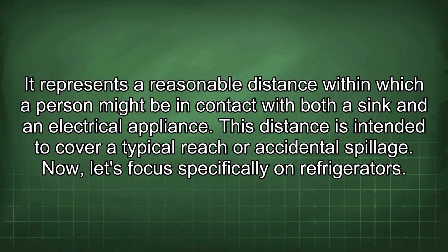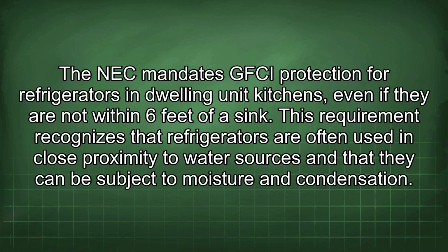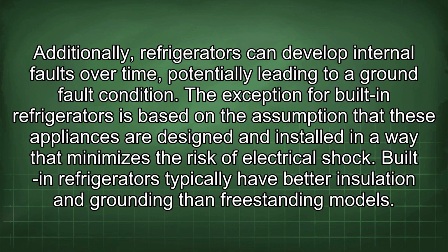Now, let's focus specifically on refrigerators. The NEC mandates GFCI protection for refrigerators in dwelling unit kitchens, even if they are not within 6 feet of a sink. This requirement recognizes that refrigerators are often used in close proximity to water sources and that they can be subject to moisture and condensation. Additionally, refrigerators can develop internal faults over time, potentially leading to a ground fault condition.